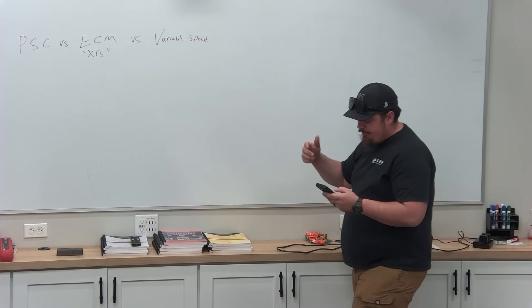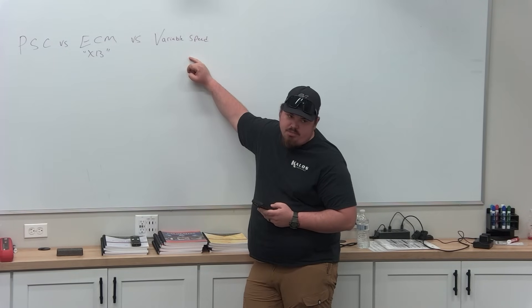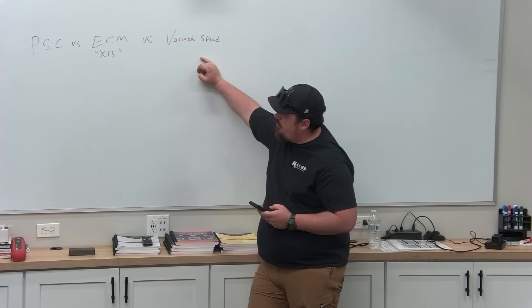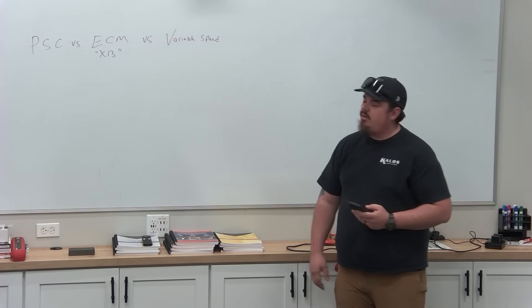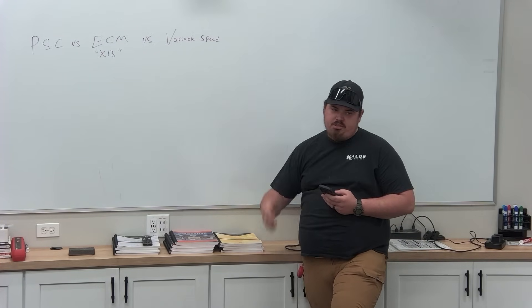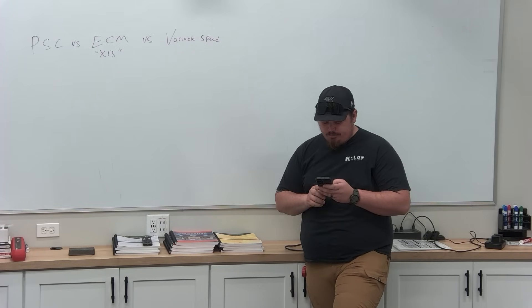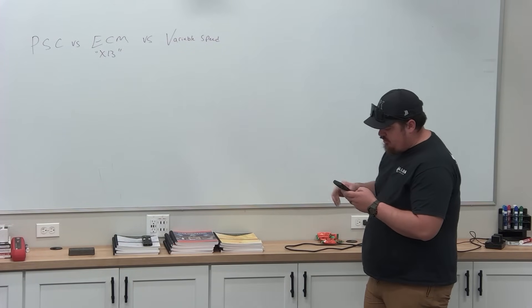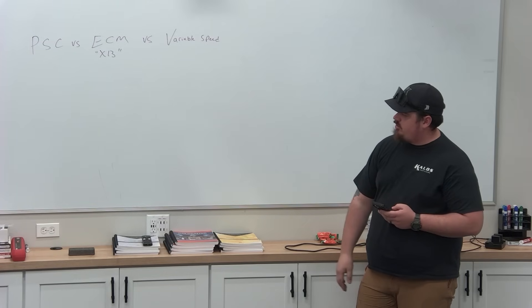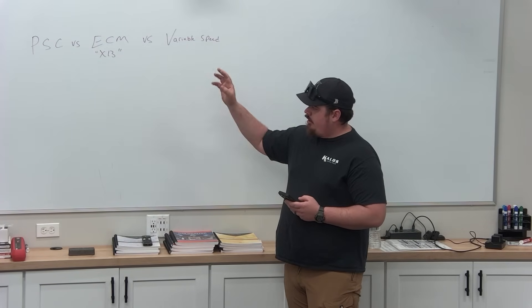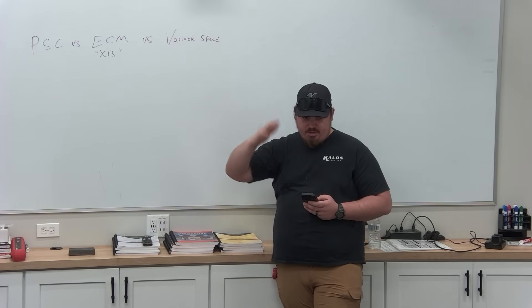Variable speed motors work off torque and can easily overcome static pressure issues. For sizing, a PSC motor will actually decrease its CFM because it doesn't know how to overcome that pressure. ECM motors and variable speeds use back EMF to determine motor torque and adjust to load conditions — they can ramp up and down very efficiently. They're a lot more efficient than PSC motors because a PSC motor is essentially single stage: 100% on or 100% off, whereas ECM can regulate itself up and down based on airflow.